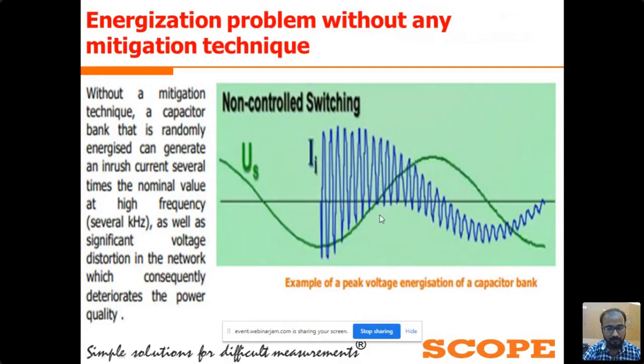In this waveform, you can see that without a mitigation technique, a capacitor bank that is randomly energized can generate an inrush current several times the nominal value at high frequency, as well as significant voltage distortion in the network, which consequently deteriorates the power quality. So to avoid that, we are trying to close the capacitor bank near to the system voltage 0.